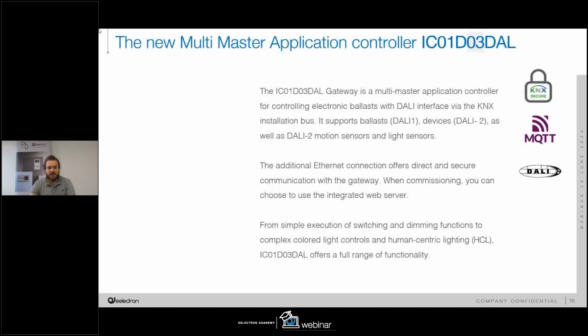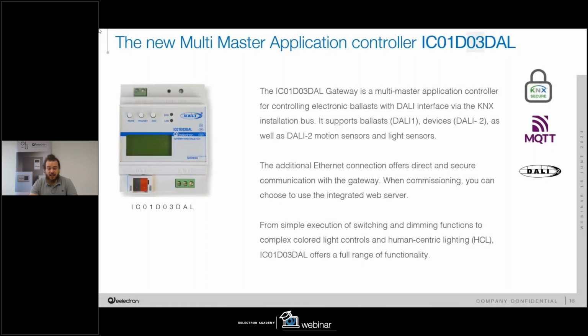Finishing with the multi-master application controller, that is our IC01D03DAL. Here we can see the picture. That is a DALI gateway with only one DALI bus, plus a KNX connection and also an IP port. The IP port can be very useful to connect this gateway and enable the MQTT protocol, for example. This means that we can integrate third parties using MQTT very easily. So all the information coming from DALI can be forwarded easily to MQTT. But also some KNX messages can be forwarded from KNX to MQTT thanks to this gateway.